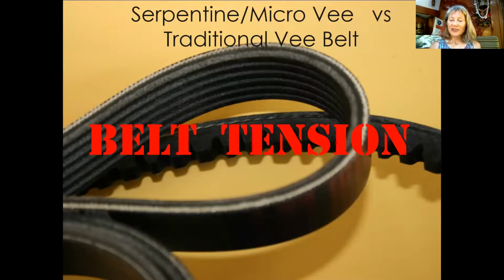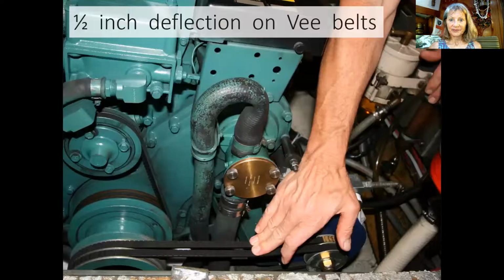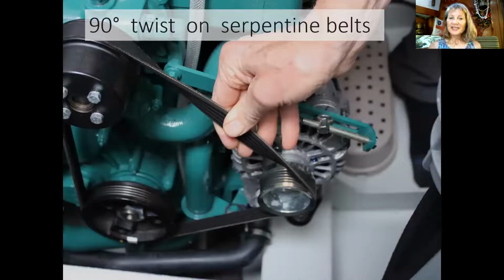There are 2 types of belts. Traditionally we used V belts, which are a deep, thick rubber belt, and that's been switched to a micro V, which is a little serpentine belt—more like a snake with little ridges rather than just one big V. 1/2-inch deflection is how much belt tension you want on the traditional V belts, and on the new serpentine belts, a 90-degree twist, so you just want to be able to twist it 90 degrees. You don't want the belt too slack or too tight.